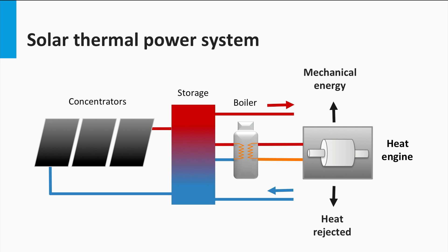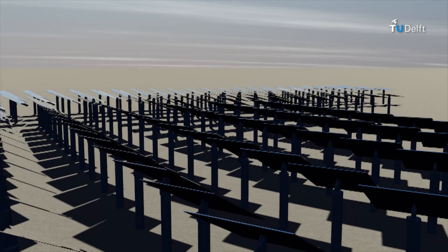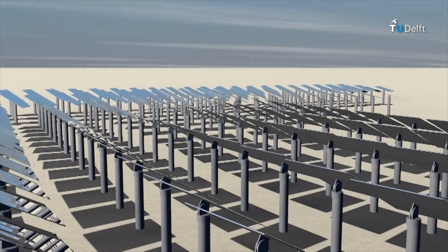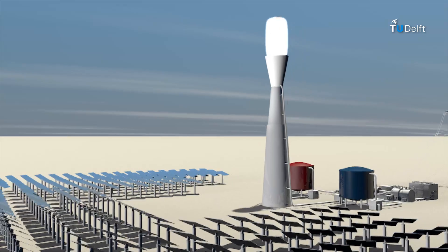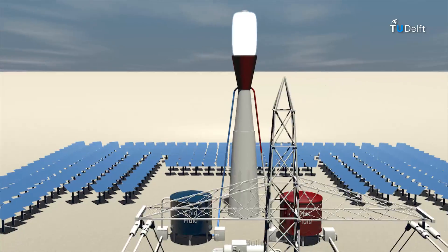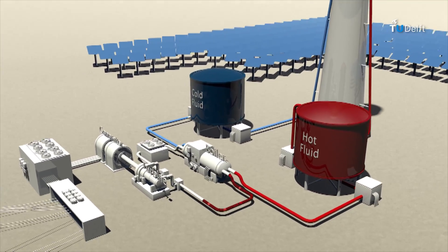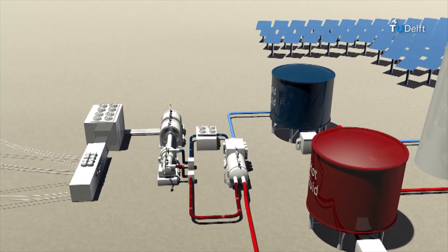I am going to explain the basic concept of solar thermal power using the example of a solar power tower, though we will see later that this is only one possible configuration of solar concentrator systems. The direct light strikes the mirror or collectors, which are equipped with a tracking system that follows the sun. The shape of the mirrors focuses the light on a central tower, where a fluid is heated to values between 100 and 500 degrees Celsius due to the concentrated sunlight. The fluid is then used to move a turbine in a heat engine and produce electricity.